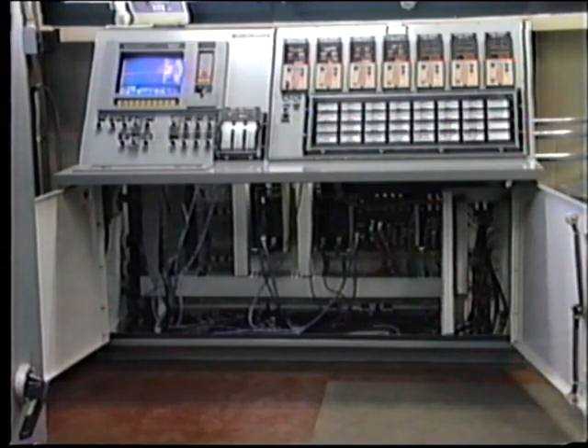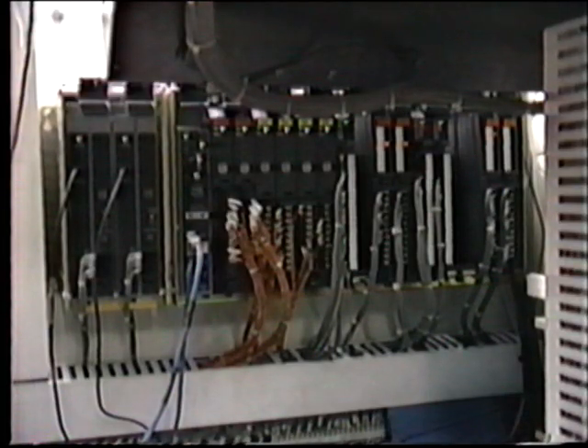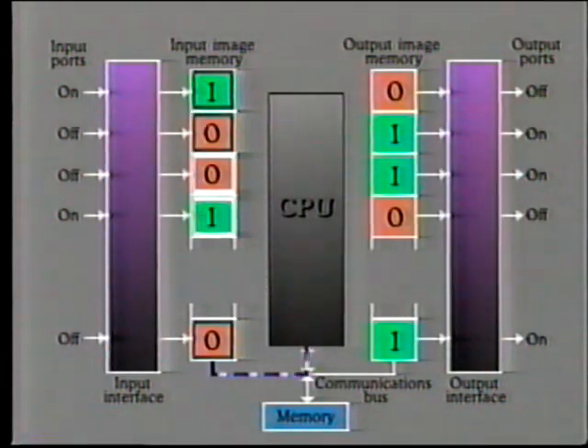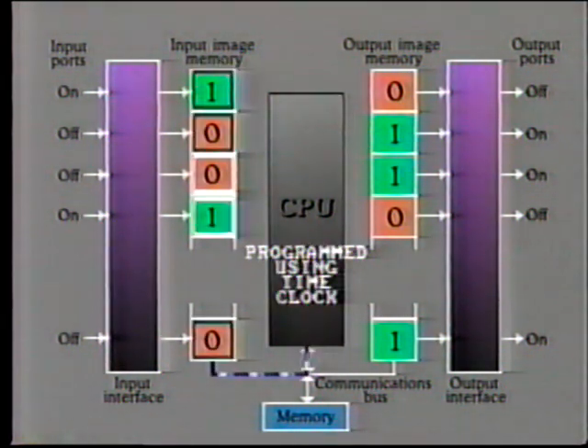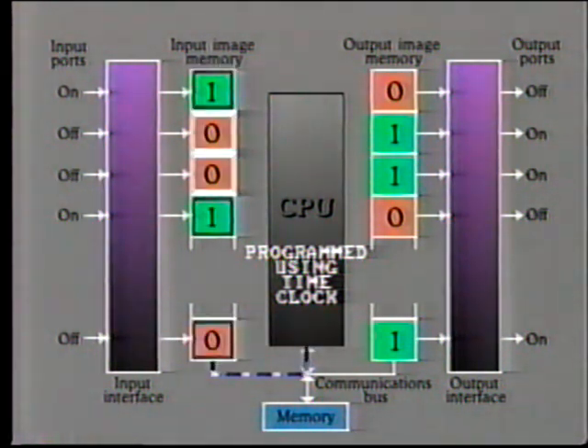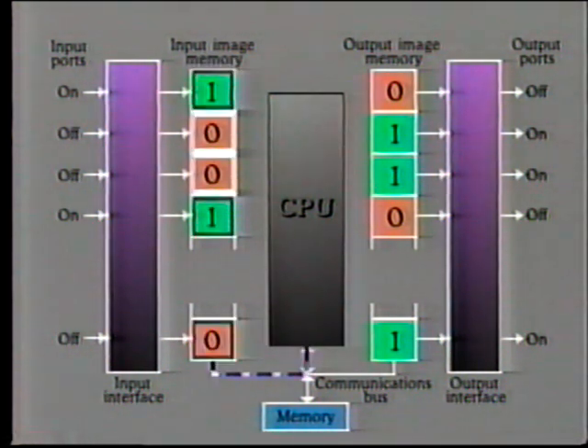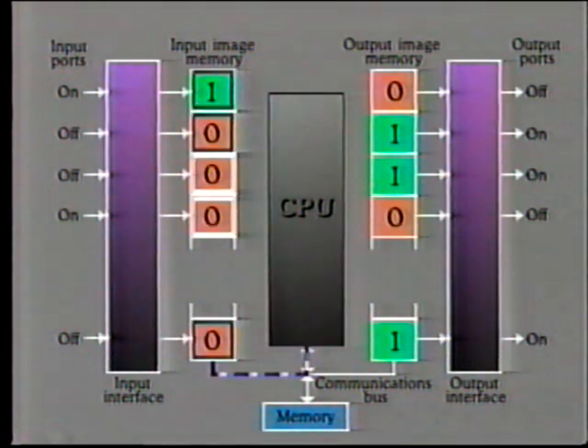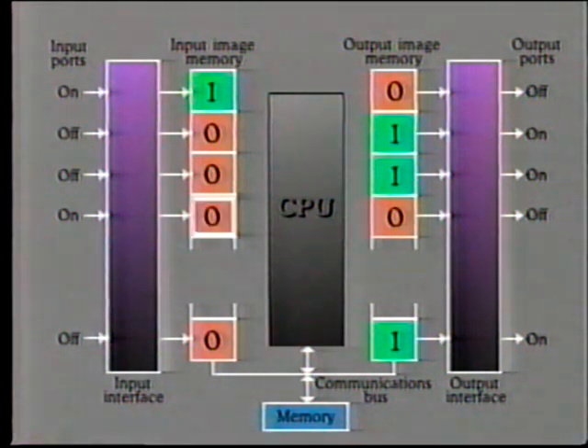However, large PLCs may need to control several independent control loops. So in this case, the time period between scans would be extended. The large CPU is said to be multitasking, and usually some order of priority is established in allotting the tasks. For example, it may be considered necessary for certain control loops to be scanned more often than others. This is programmed into the PLC using the time clock. Over and above this, an emergency condition, say a machine alarm, may direct the CPU to interrupt its existing task and switch to the emergency item.